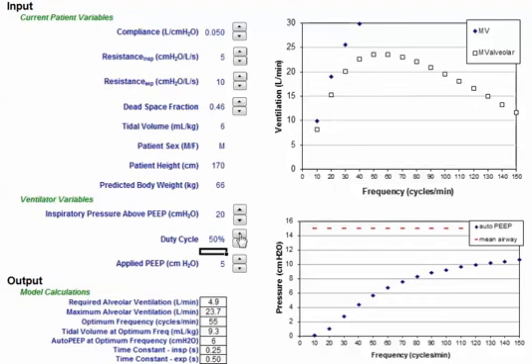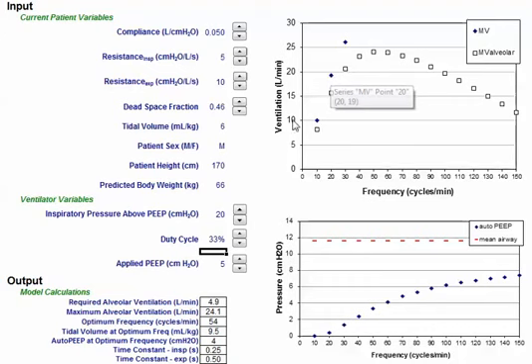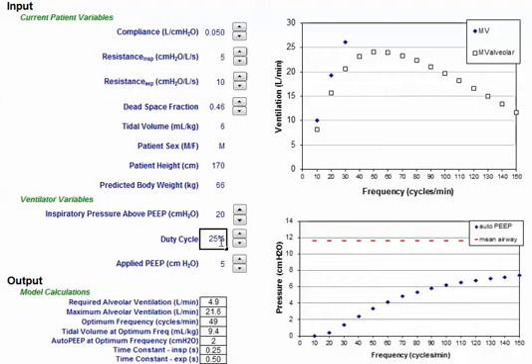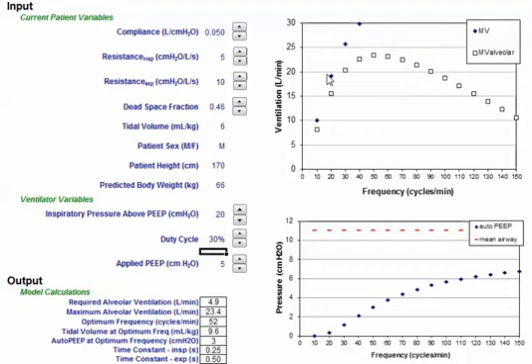If we look at a respiratory rate of 20, based on this compliance and pressure, I should be getting 20 liters per minute, and I'm not. So in this scenario, a duty cycle that's less than 50% or 1 to 1 is more ideal. I'm going to change this to a 1 to 2 IE ratio, and you notice I'm getting closer to my max minute ventilation. Let's try 25% or 1 to 3. An IE ratio of less than 1 to 1 is going to get us as close to our max minute ventilation obtainable.